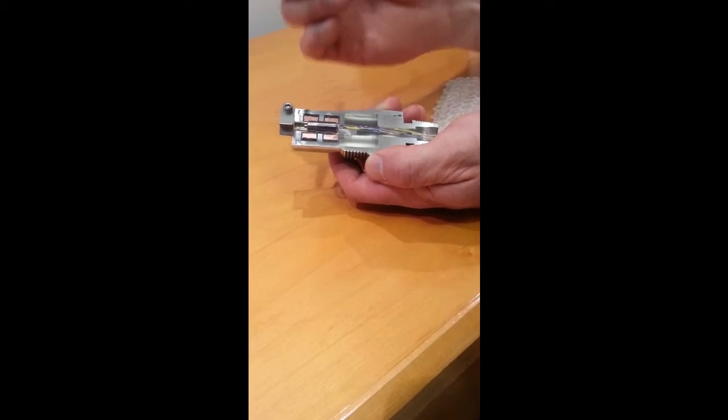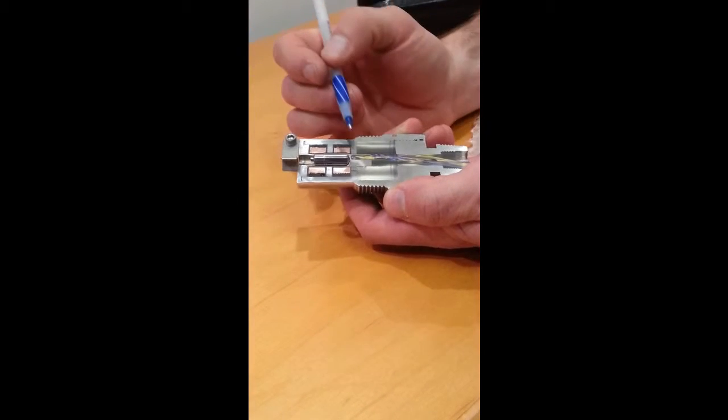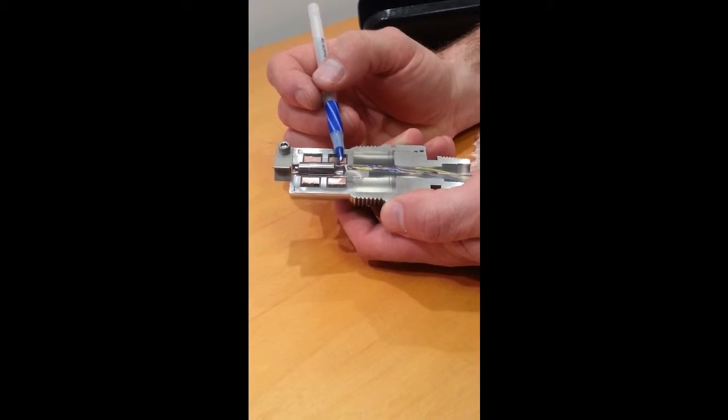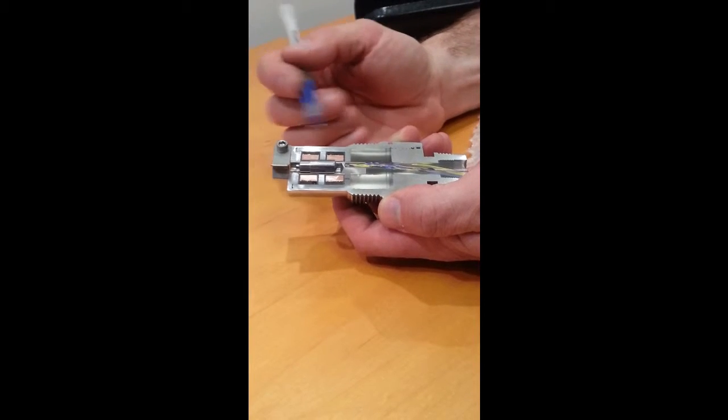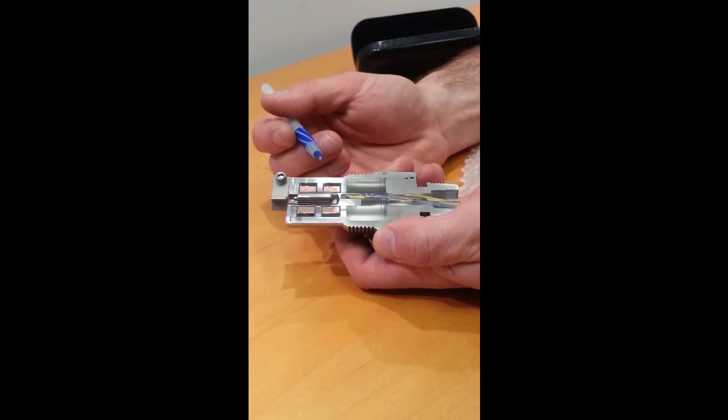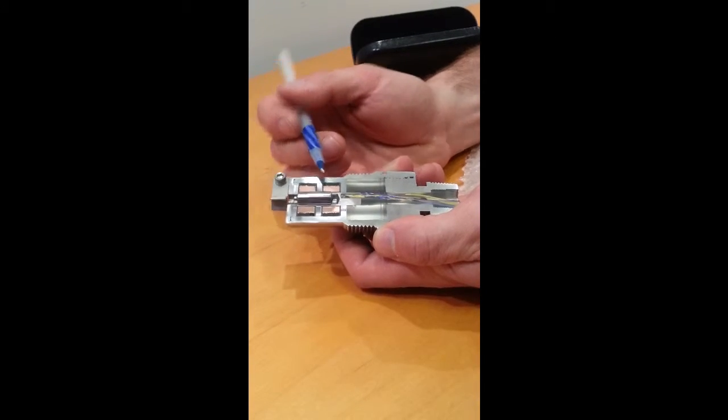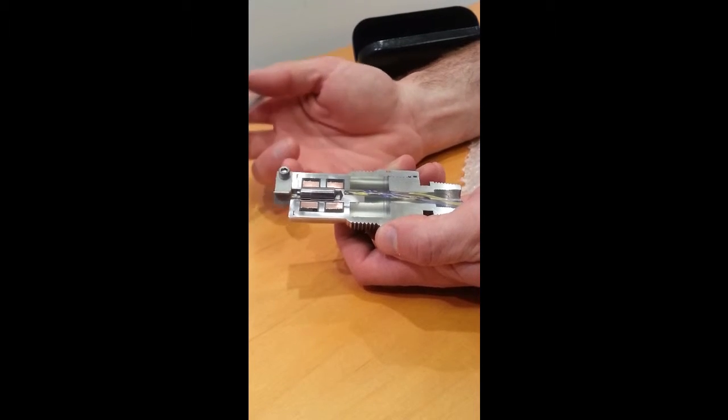The constant piston's motion is keeping your sample clean and refreshed all the time. It's also keeping the sensor very clean. This motion creates lots of turbulence in there, so it's self-scrubbing. So the goal is to have our customers use these where they are using them maintenance-free, not lots of cleanup or anything like that.